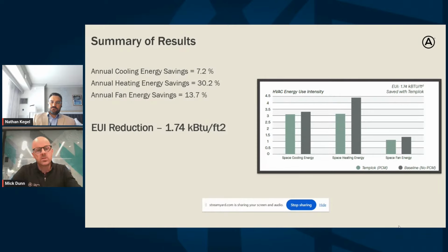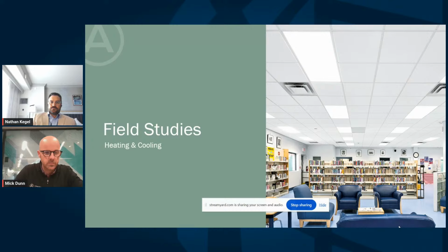The general results of this project were about a 7% reduction in cooling, a 30% reduction on the heating side, and about a 13% reduction on the fan energy side. If we began to modify and stretch out those results using controls, which is what Nathan was showing earlier, we would expect those fan energy savings to come down because we'll use a little more fan energy in the interest of boosting that cooling energy a bit further. But here we're seeing an EUI reduction of about 1.75 kBTUs per square foot, a meaningful indicator that this can help with things like meeting LEED credits, but also satisfying various code requirements for energy code goals.